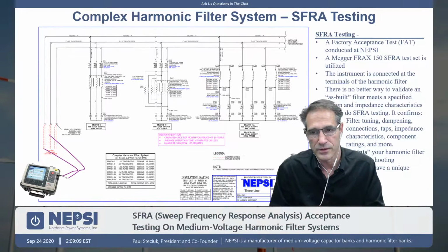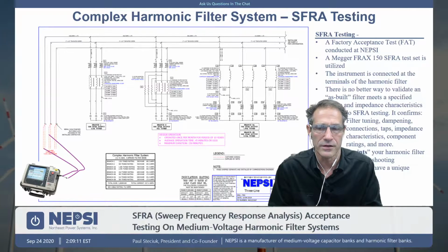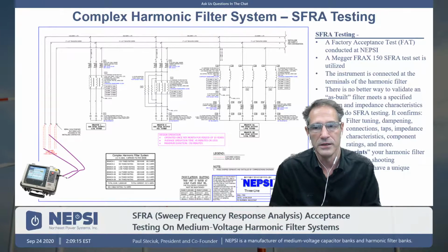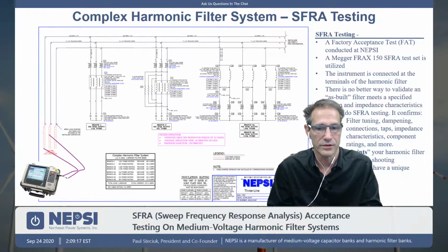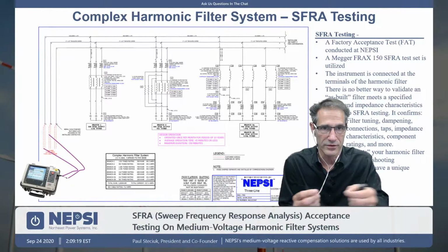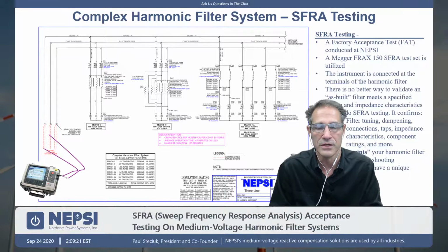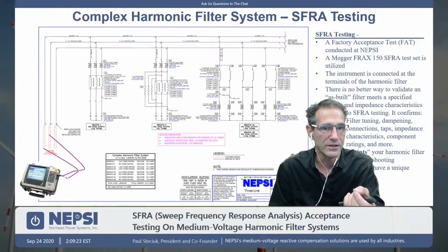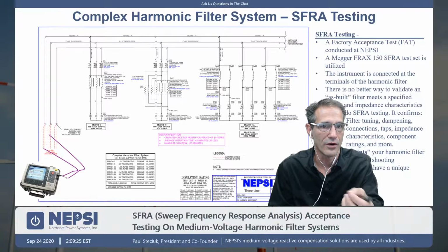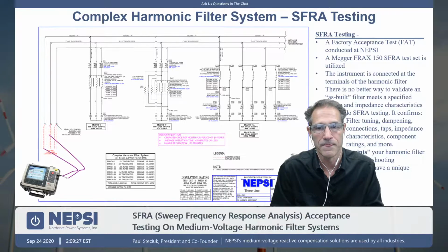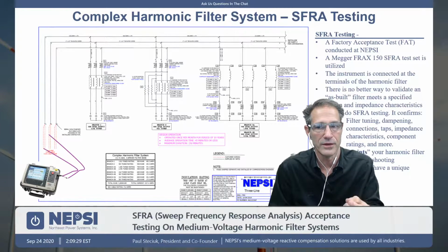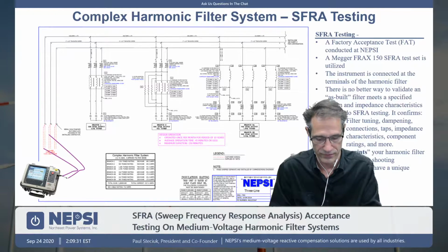And this device is very sophisticated. It's doing sometimes 10 samples per frequency point. And what we are able to do is determine what is the impedance throughout the whole range of that harmonic filter, but not only impedance, but also X and R, the phase angle, and more. So we really are able to get a very good characteristic of the filter.